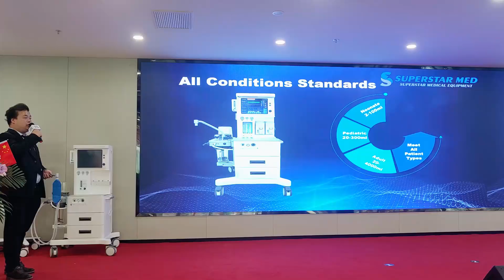This is the ventilation mode which this machine has, and this is also the new design for new products. We know before actually for all kinds of different products, maybe for example for the basic one, it only had the volume control and using the mechanical valve. But for this one, all models are using the electric proportional valve. So it means when you are setting any of the parameters, it will be very accurate, especially for PEEP and tidal volume. It will not go high and down, it will always be stable. Anytime you set the parameters, after one breathing cycle, it will provide the new data.